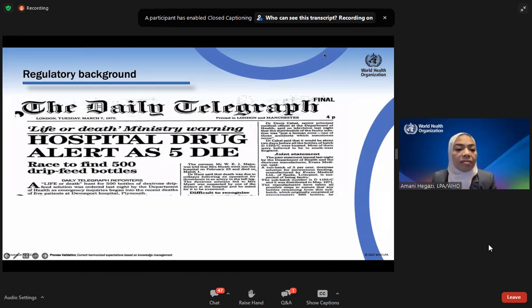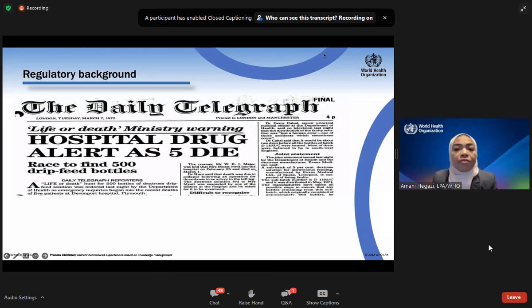famous tragedy that happened in 1972. Last March, we marked the 50th anniversary of this tragedy. It is the Devonport tragedy, where five people died due to the administration of 5% dextrose injection that was not properly sterilized. The thorough investigation revealed that the autoclave used for sterilization was functioning faultily relative to air displacement, which resulted in inappropriate sterilization. Hence non-sterile product with a high contamination of gram-negative bacteria was injected, which caused endotoxic shock for several patients.